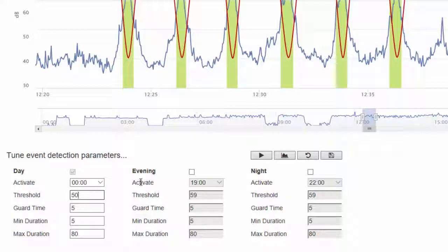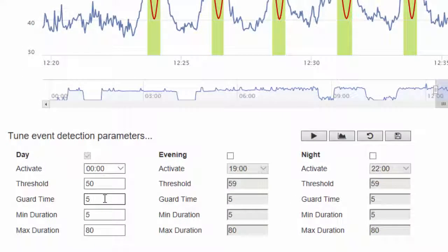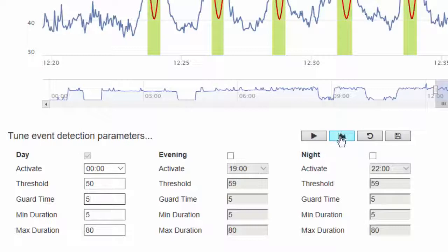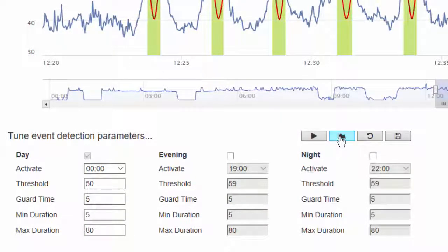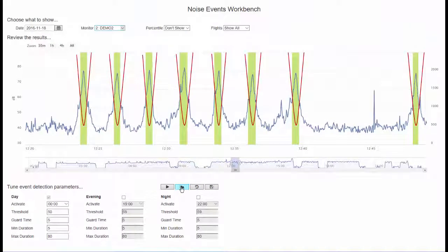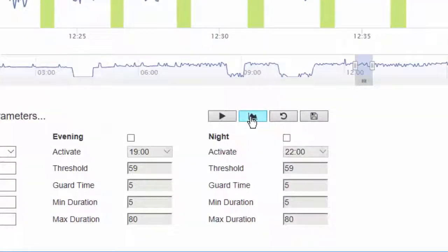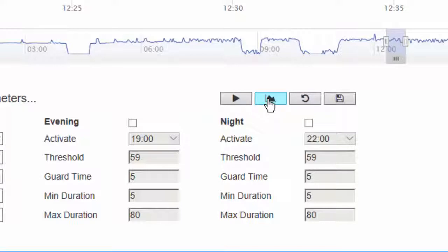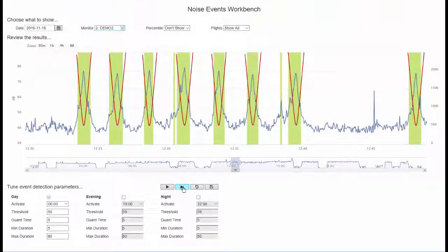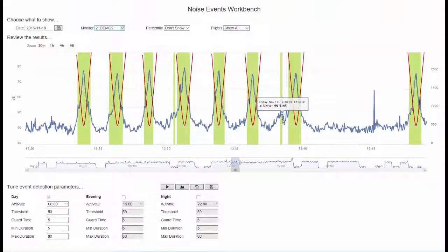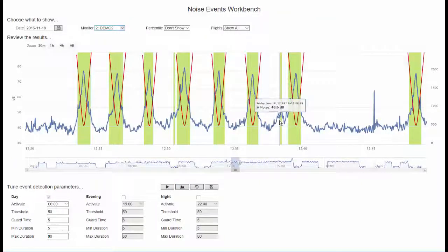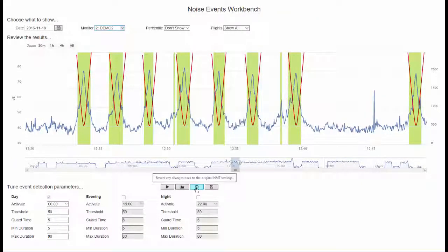The threshold settings are here. There are also 3 different templates available if you wish to have different settings at different times of the day. Otherwise the first set of parameters applies at all times. So we change the threshold to 50 dB and click this button which will reassess the data based on the current settings. And we should see the graph change. Now a false positive has appeared where the noise level was above the new threshold for longer than the minimum duration.